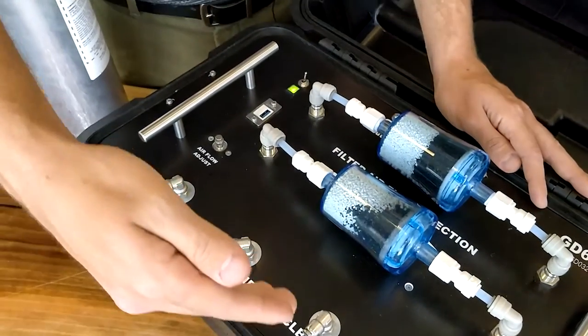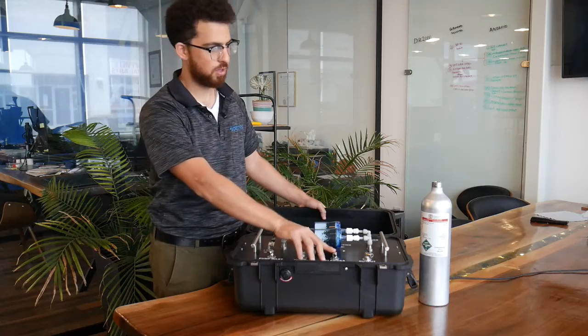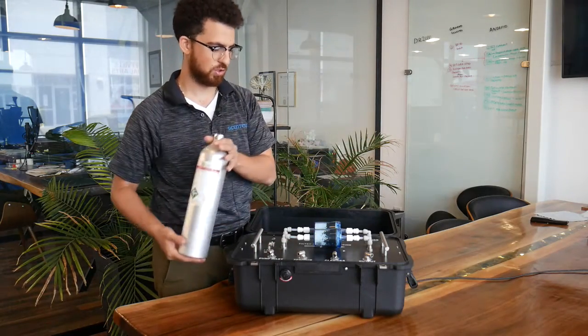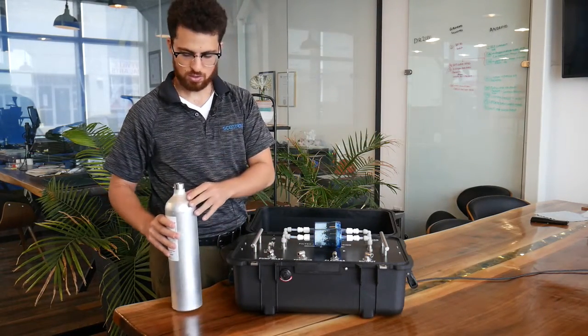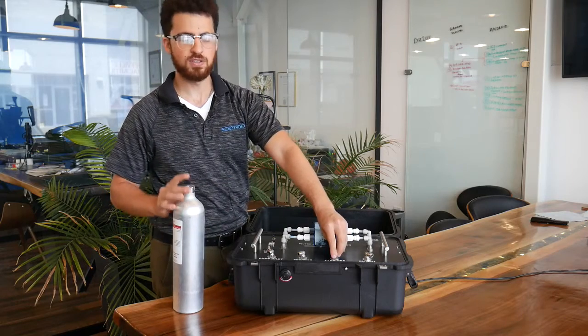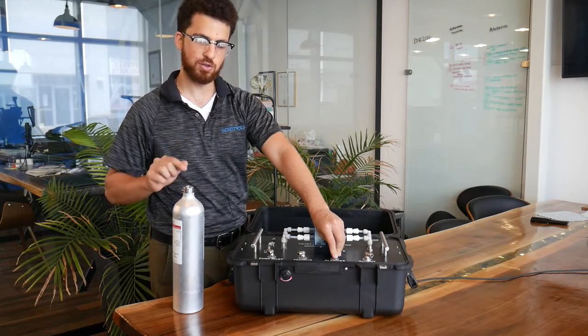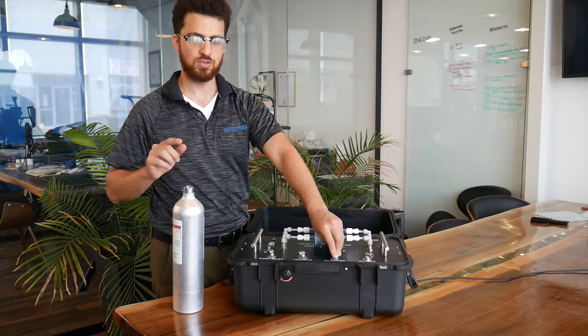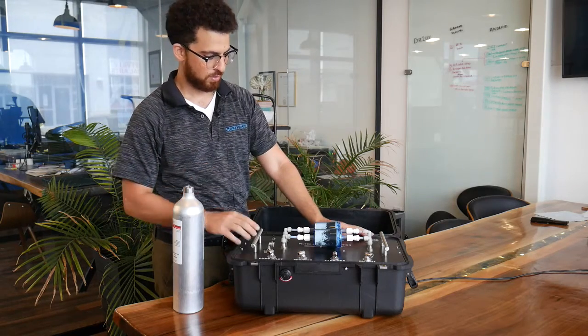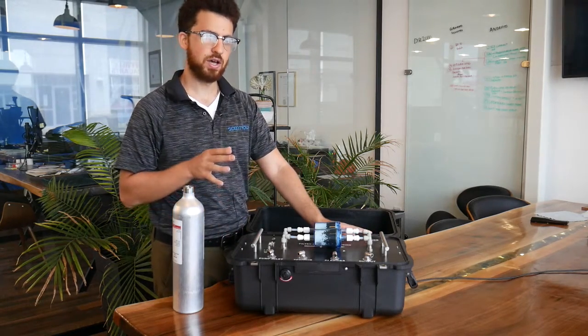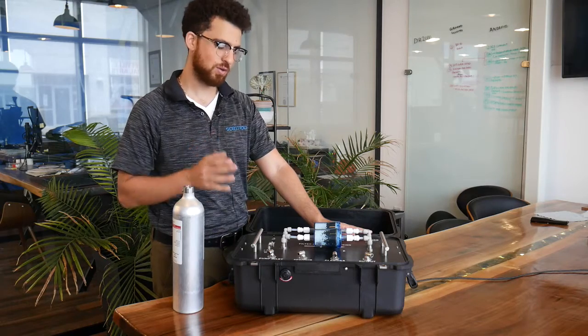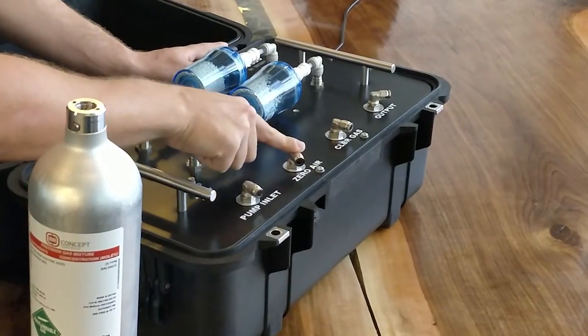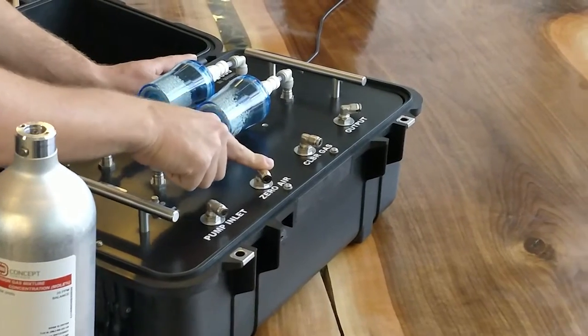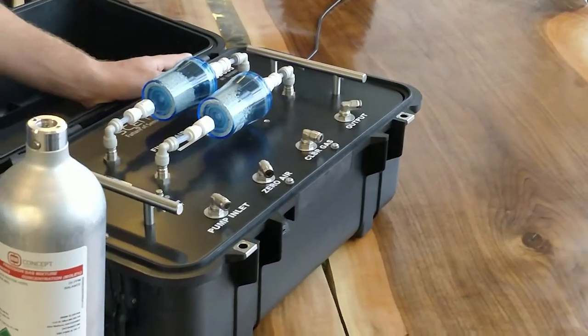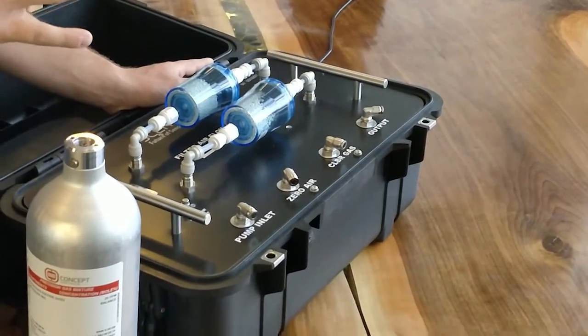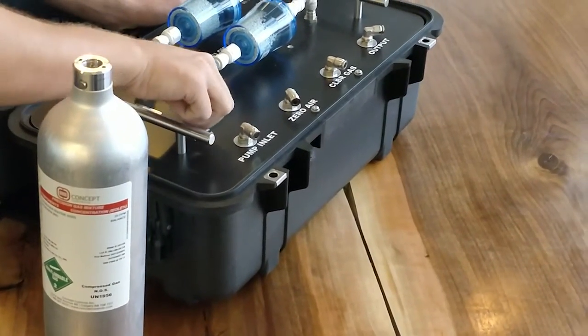The calibration gas that goes in here needs to be a compressed cylinder. You can see this is the typical cylinder that we use. You would put on a fitting here and put into here. It is important to note that the fitting flow should be more than 600 cc. Optionally, if you wanted to use N2 or your own zero air instead of using your pump, that would go in this port here. Again, this would need to be compressed. Typically, we have the pressure around 40 to 50 psi.